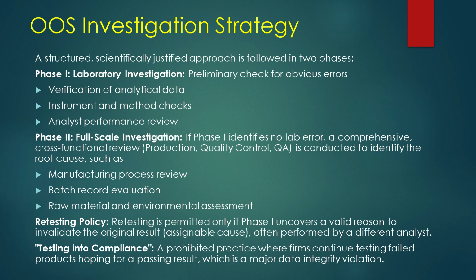Retesting policy. Retesting is permitted only if phase 1 uncovers a valid reason to invalidate the original results, often performed by a different analyst. Testing into compliance is a prohibited practice where firms continue testing failed products hoping for a passing result, which is a major data integrity violation.